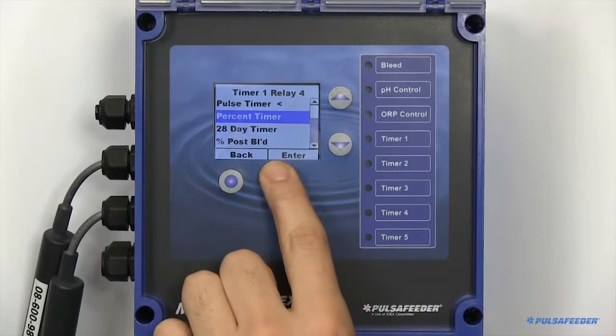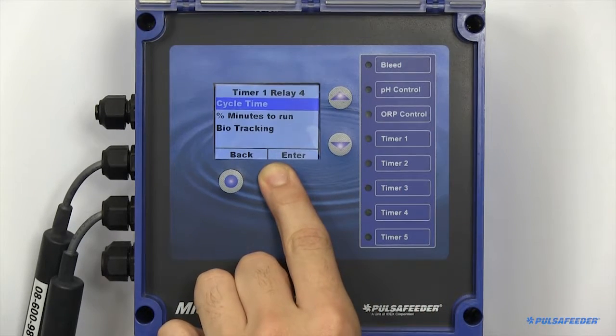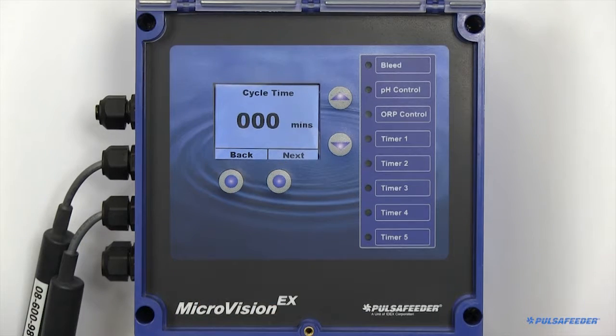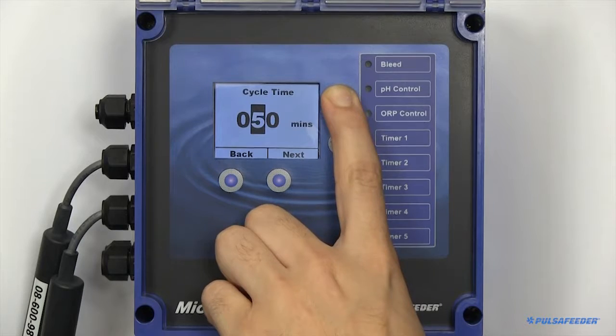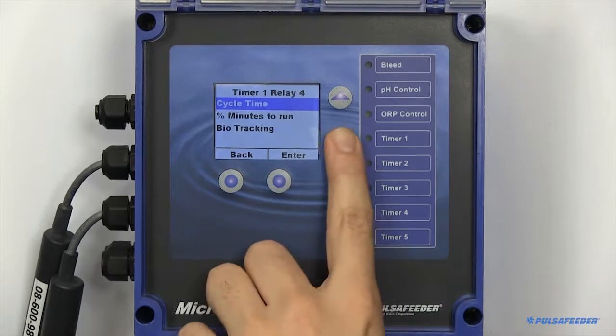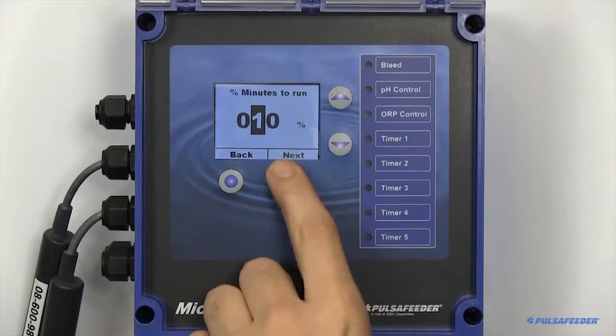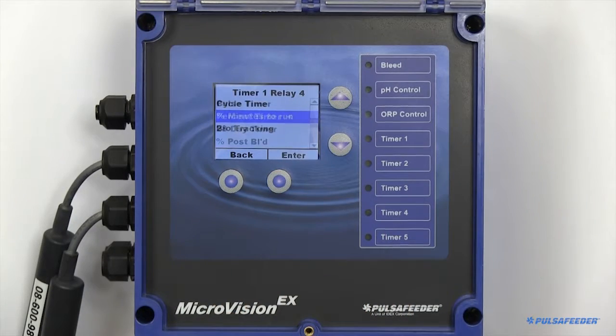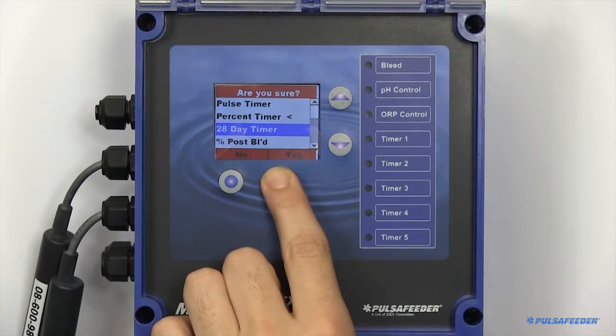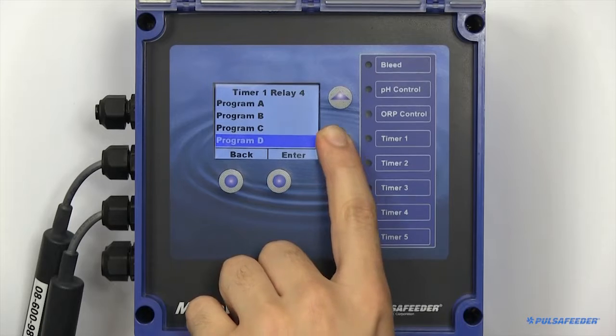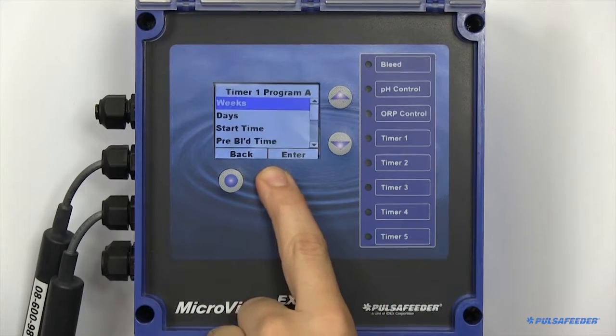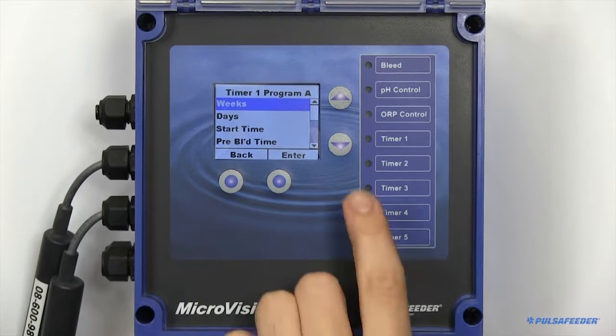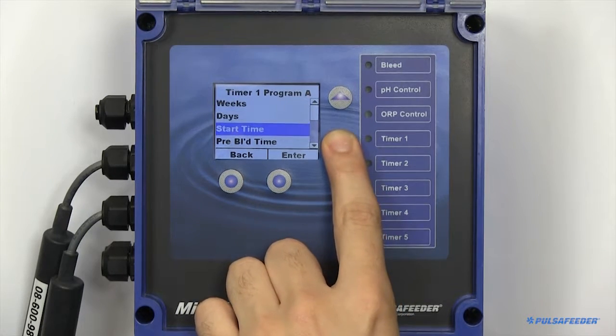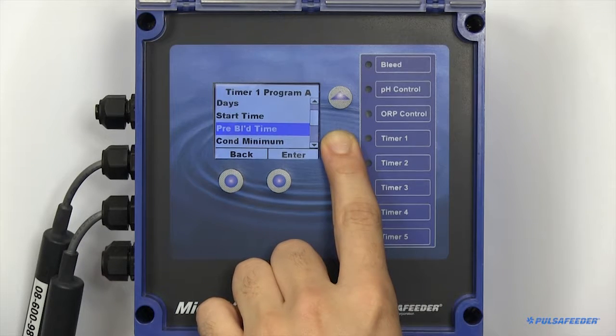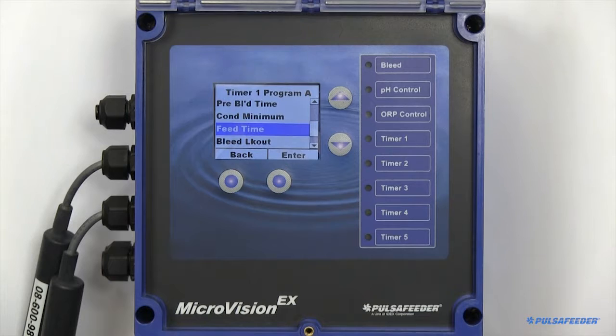There are two parameters when setting up a percent timer. You will need to set your cycle time and your percentage of minutes you would like the timer to run. For example, 10% of 60 minutes would be 6 minutes of feed time every 60 minutes. A 28-day timer, or biocide, can have 4 programs running on each relay. To set up a single program of a biocide timer, you need to configure the weeks, days, start time, feed time, and if applicable, specify a pre-bleed, minimum conductivity, and bleed lockout.